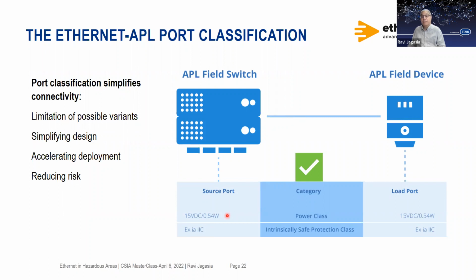15 volt DC, 0.54 watts is the approximate power, one of the power classes available, where you can define on the source side, on the field switch side, and then see that the APL field device also is having the same load. And then you will also ensure entity parameter comparison.